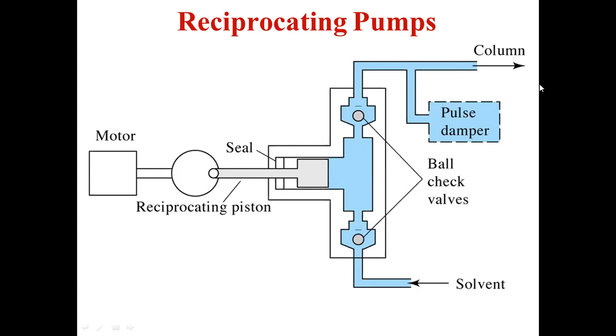A motor-driven piston will be creating the pressure in order to make the solvent flow towards the chromatography column at a fixed pressure, at a fixed flow rate. And this is the commercially available reciprocating pump. You can see the terminals here, and by means of the terminals, we can make the mobile phase move towards the chromatography column. This is a motor. This motor will be running in order to create the pressure. At the created pressure, the solvent will be sucked from the solvent reservoirs, and we can regulate and monitor the fixed flow rate by means of this flow regulator, and ultimately connect to the column. So this is the terminal to connect to the column.